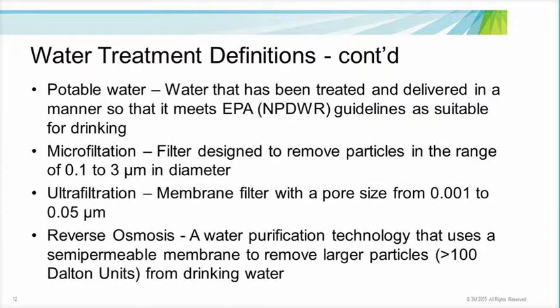So more of these water treatment definitions include potable water, which is water that has been treated and delivered in a manner so that it meets EPA National Primary Drinking Water Regulations guidelines and is suitable for drinking. The expectation is that the feed water that comes into the facility is potable water. Microfiltration utilizes a filter designed to remove particulates in the range of 0.1 to 3 microns. Ultrafiltration utilizes a membrane filter with a pore size of 0.001 to 0.05 microns. And reverse osmosis is the water purification technology that uses a semi-permeable membrane to remove large particles from drinking water.